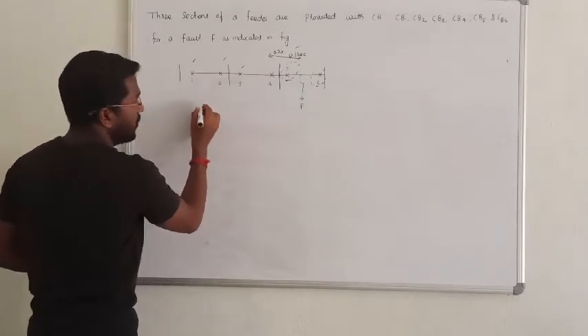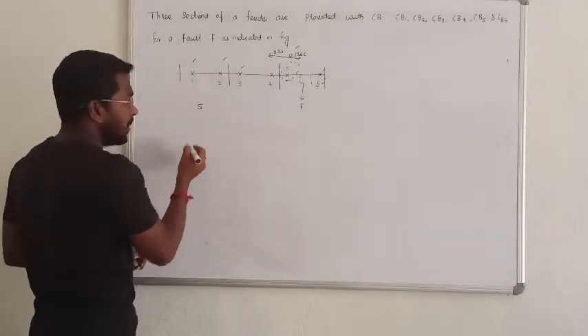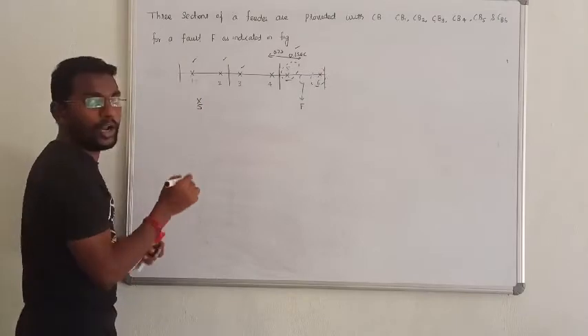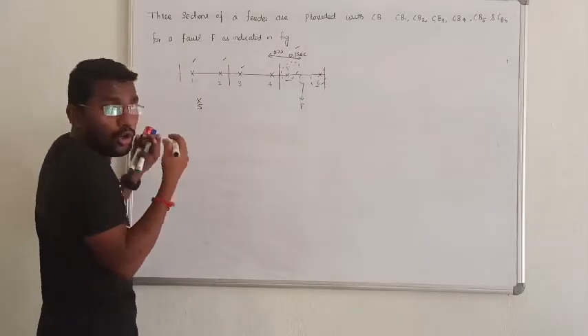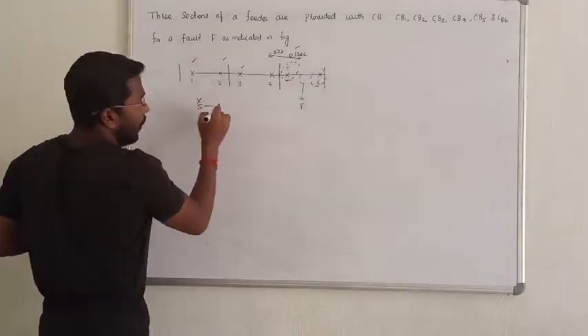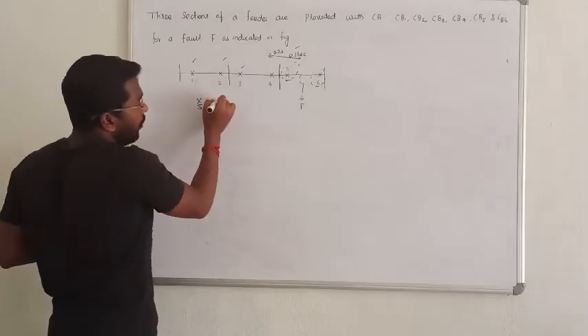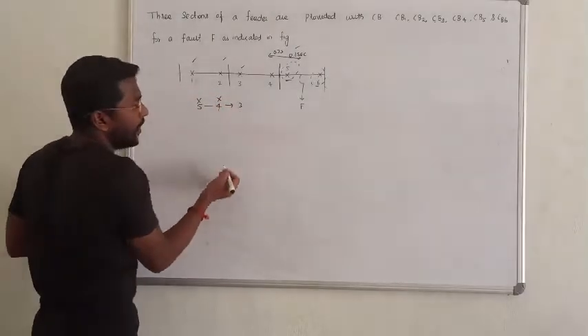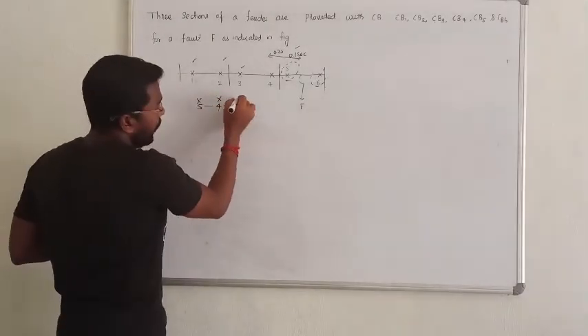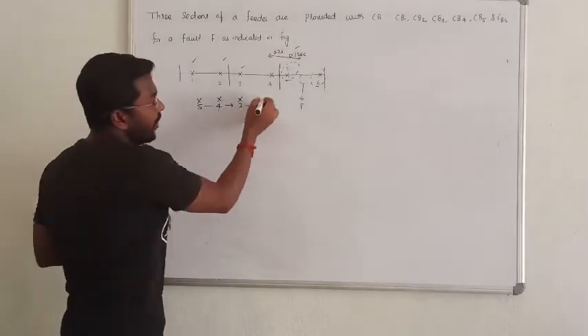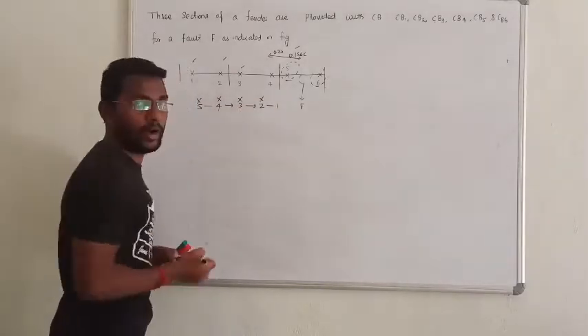Now, what is the sequence? Circuit breaker 5 will operate first. If 5 fails to operate, then relay 4 will operate. If relay 4 fails, then relay 3 will operate. If relay 3 fails, then relay 2, and if relay 2 also fails, then relay 1 will operate.